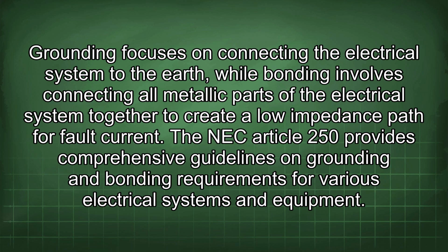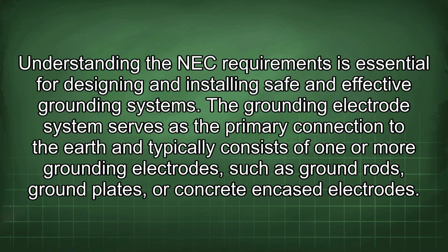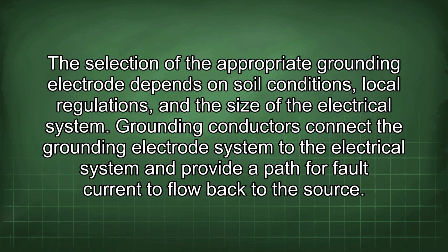The NEC Article 250 provides comprehensive guidelines on grounding and bonding requirements for various electrical systems and equipment. Understanding the NEC requirements is essential for designing and installing safe and effective grounding systems. The grounding electrode system serves as the primary connection to the earth and typically consists of one or more grounding electrodes, such as ground rods, ground plates, or concrete-encased electrodes. The selection of the appropriate grounding electrode depends on soil conditions, local regulations, and the size of the electrical system.